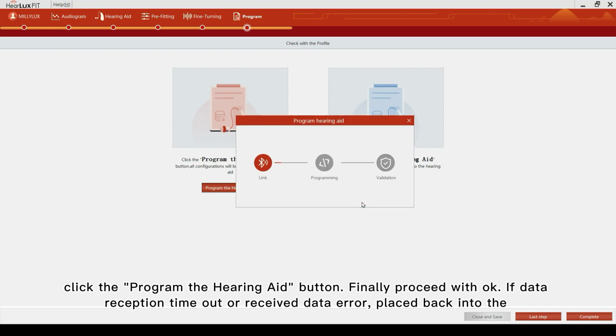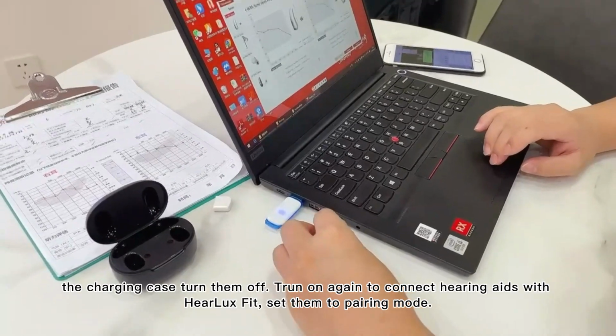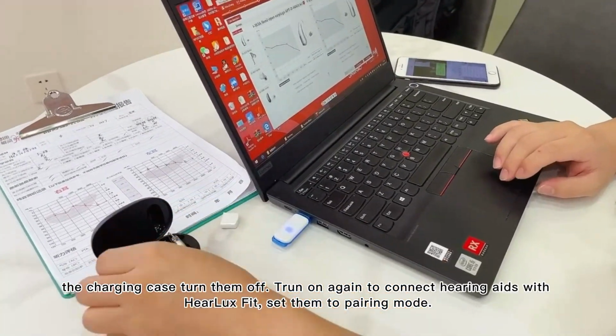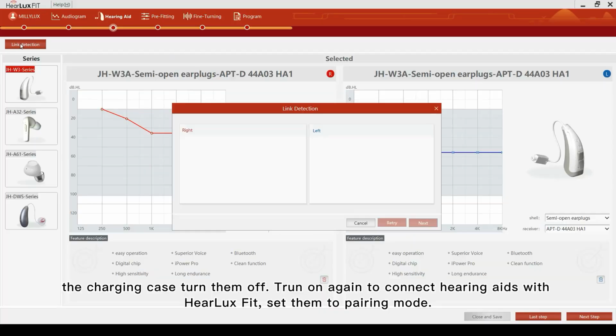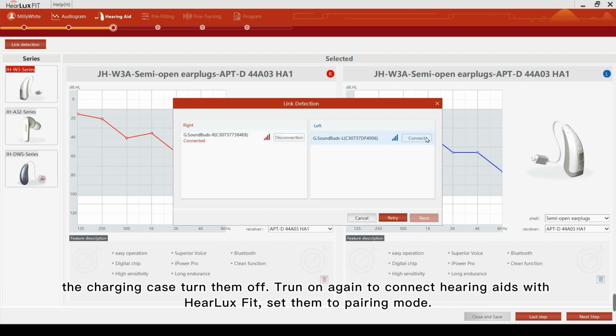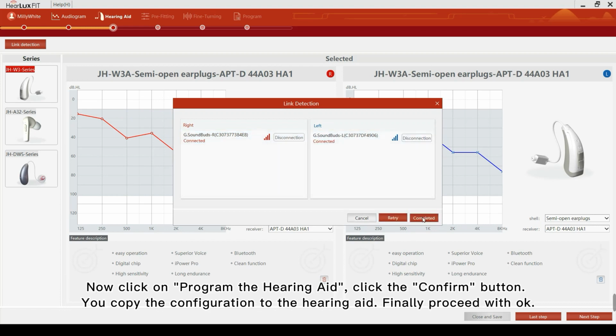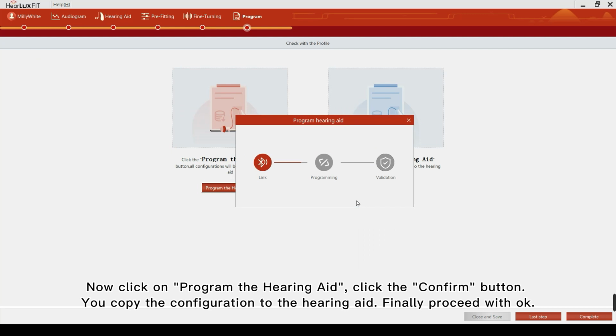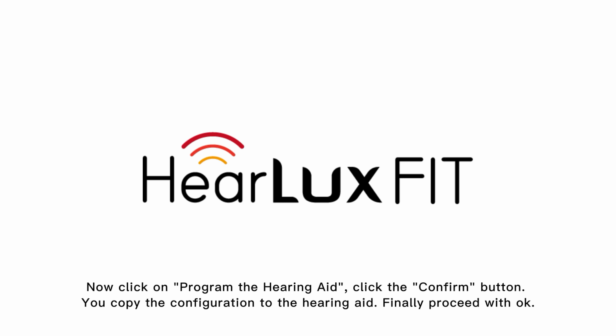If a data reception timeout or received data error occurs, place the hearing aids back into the charging case and turn them off. Turn them on again to connect the hearing aids with HearLux Fit. Set them to pairing mode. Now click on the Program the Hearing Aid button. You copy the configuration to the hearing aid. Finally proceed with OK.